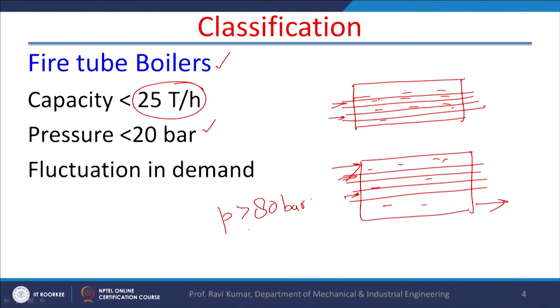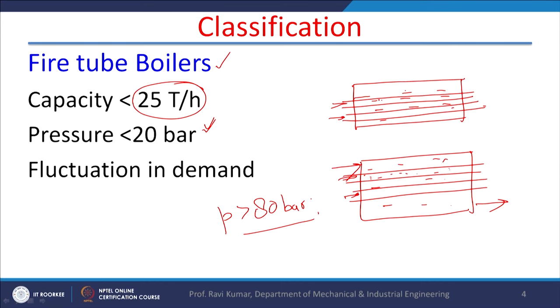High pressure boilers are those where pressure is greater than 80 bar, and between 20 to 80 bar they are intermediate pressure boilers. Fire tube boilers are normally low pressure boilers because when the shell is filled with steam at high pressure, a robust design of the shell has to be made — it is not very cost effective, the boiler also becomes heavy, and there are safety-related issues. So normally high pressure boilers are made as water tube boilers, because the high pressure of fluid will be inside the tubes only, and the shell will be filled with flue gases which are at atmospheric pressure.